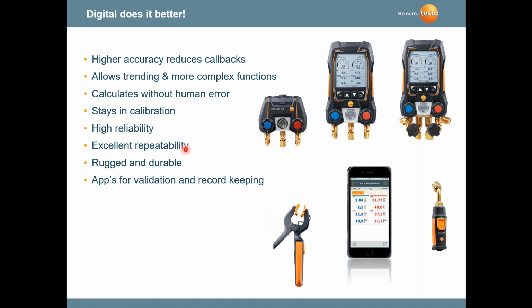Another big one here, and as I see today too, the younger technicians coming into the field, is that the instrument provides excellent repeatability. That means if someone that has 30 years experience or 3 months experience in the field hooks the blue hose to the low side, the red hose to the high side, the yellow hose to the center port, and connects the two temperature pipe clamp probes, one to the suction line, one to the high side liquid line, the results are going to be the same, regardless of how many years of experience you have. There's no calculations. There's no method of performance or procedure method. All you really need to do is make sure that the probes and the hoses are connected correctly.